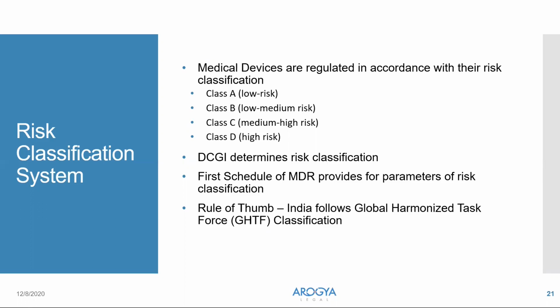I think the rule of thumb, even before going to the schedule to see how a product is going to be regulated, is to see how the product is regulated in countries which have adopted the GHTF classification, which is the Global Harmonization Task Force regulatory classification of medical devices. India largely follows this. And just another rule of thumb is that we are very close to how Singapore regulates medical devices. So the risk classification of a device in Singapore is perhaps going to be the same that India will adopt. If the risk classification that we have put out today is lesser than what it is in Singapore, eventually it will be increased. So the risk classification will go up because we try to follow Singapore to the extent we can.